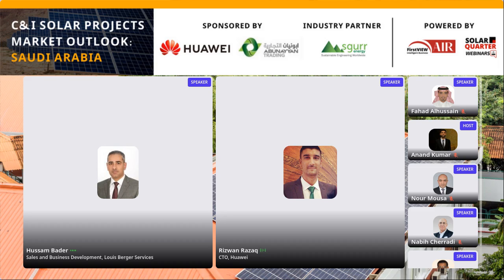Going forward, inverter technology and the number of MPPTs will be a key factor. In the next generation, rather than just having a string inverter, there will be a bipolar solution where the MPPTs are still in the field, with a DC circuit between the controller in the field and the main inverter, which will be localized at the transformer station. The MPPT feature is very important for high current PV modules, whether connecting two strings, one string, or even four strings into an MPPT, and this can be accommodated with the latest inverter technology available from Huawei.